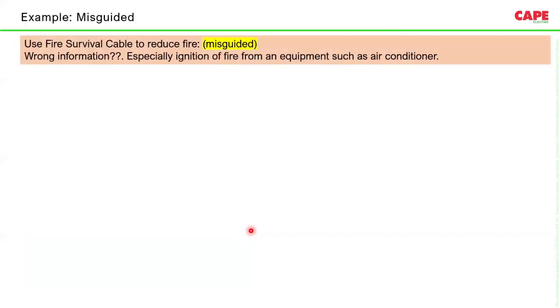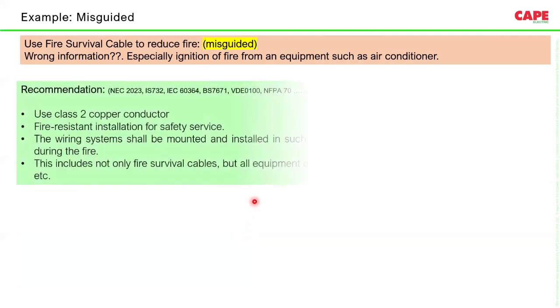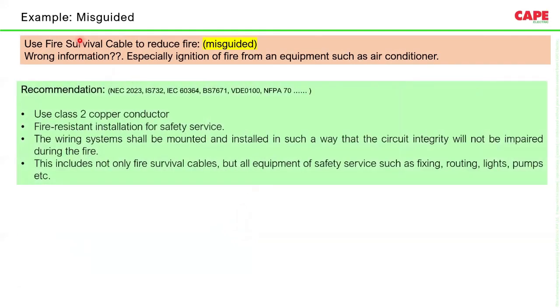So another misguided system is sometimes the belief that fire survival cable can reduce fire. For example, in one report I have seen that there was an air conditioner fire, and the report says all wires should be fire survivable. Actually, this is again not the correct information. The fire started from the air conditioner. Even if you use a fire survivable wire, the problem is in the air conditioner, not in the wire.